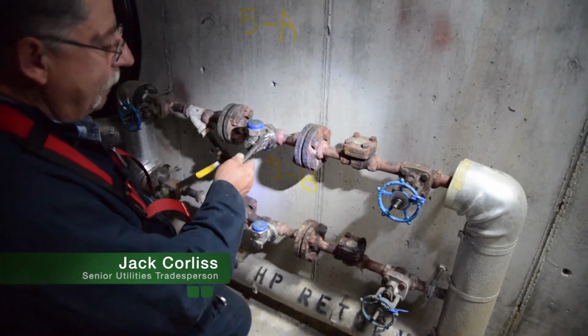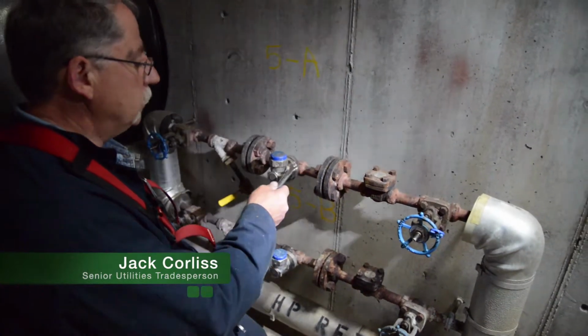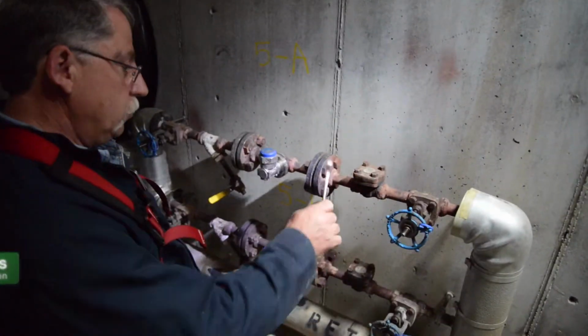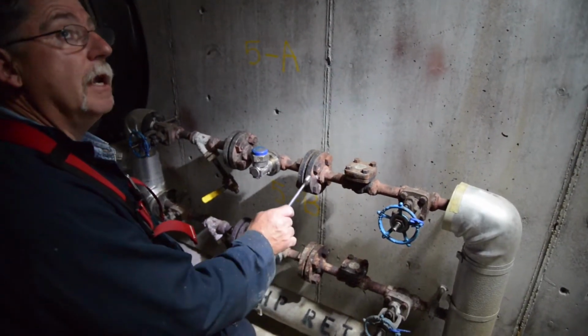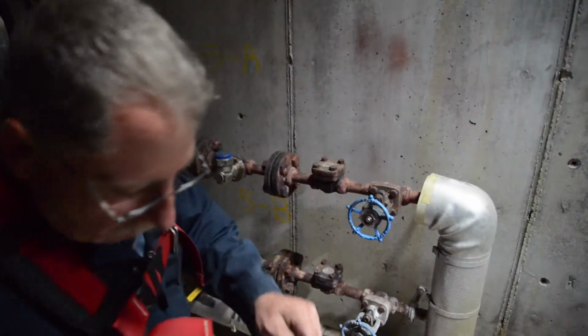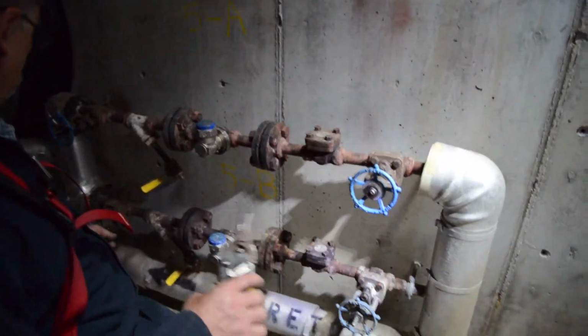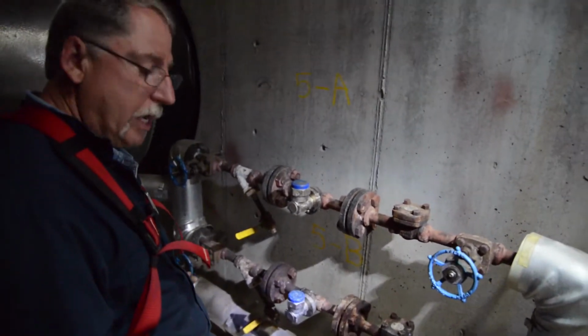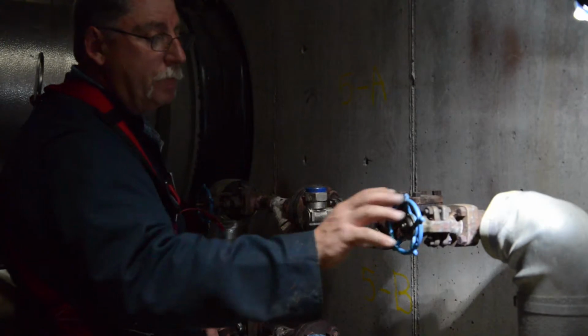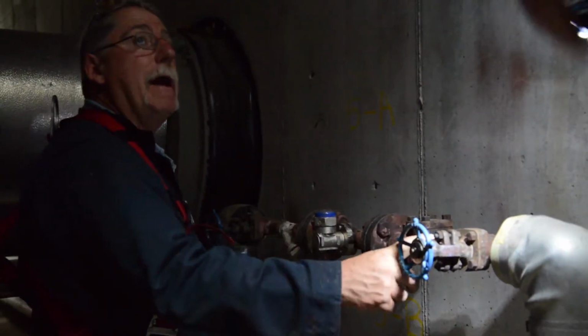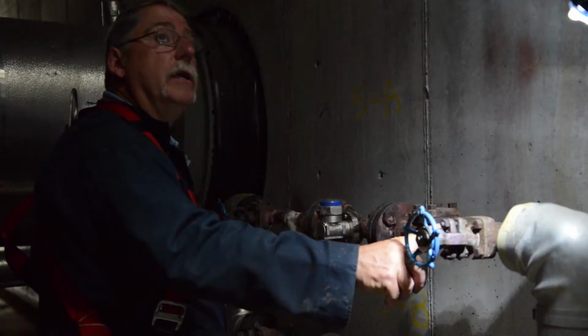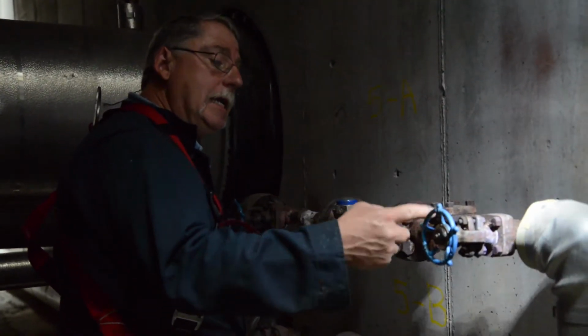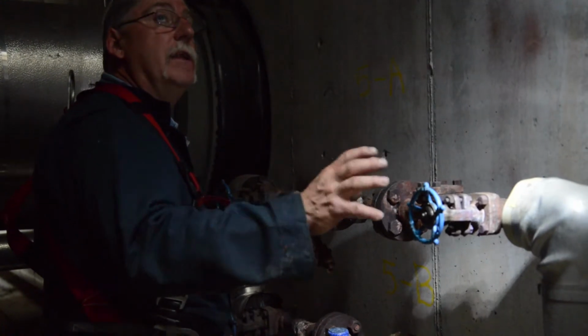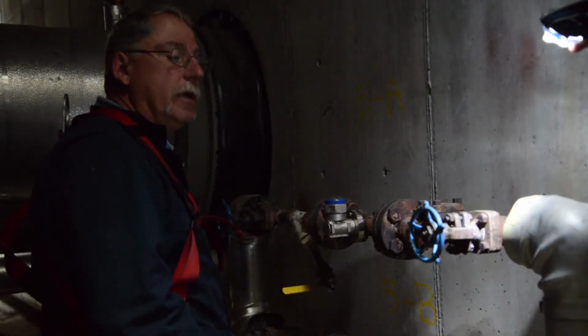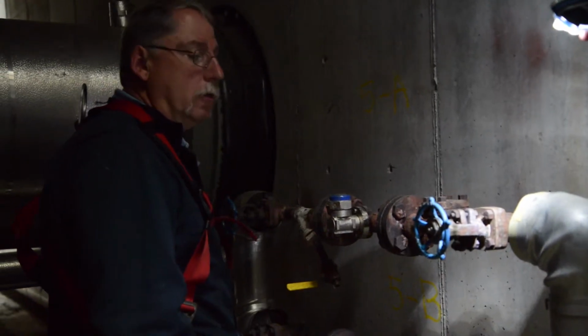Every other year we change the traps out. We do South Campus this year, North Campus we'll do next year. And there's 2 trap stations in case one fails, and then the other one will take over. We put these tags on them just to let us know what's been done and what hasn't been done. We change colors every year. Next year we would take this whole bonnet off, take all the packing out and repack it with everything new. And that's good for 3 years. We just come again and tighten it in just to seal it if we needed to add, but we wouldn't pull. About every 3 years we pull it all out and put all new packing in.